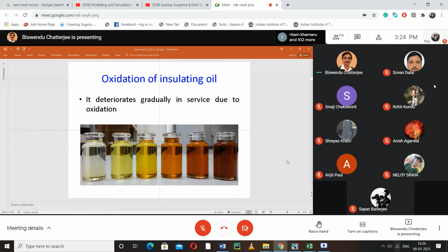Now another important point is what is called sludge in transformer oil. What is there in a transformer? A heating part, that is the winding, and the circulating oil. Now what happens? You cannot make the transformer totally sealed and isolated from atmospheric oxygen. Some part of oxygen will always remain in the transformer. Oil on reaction with this atmospheric oxygen forms acid, because oil is a hydrocarbon, and oxidation of hydrocarbon leads to acids.